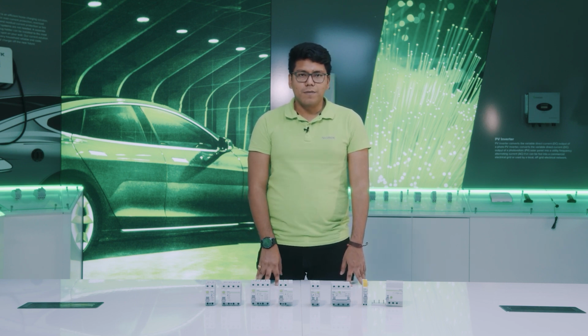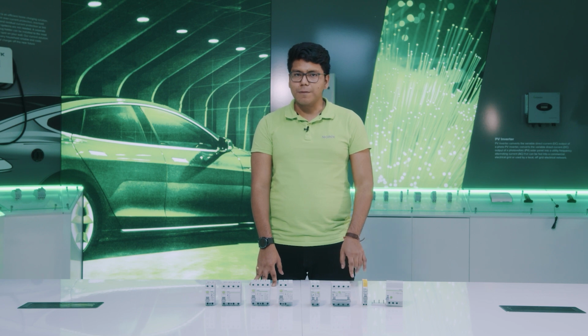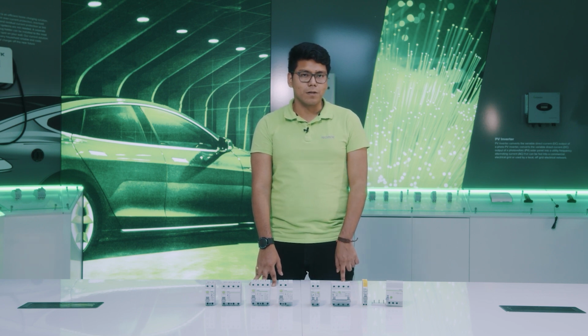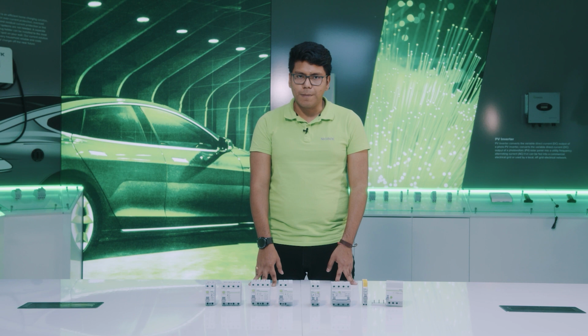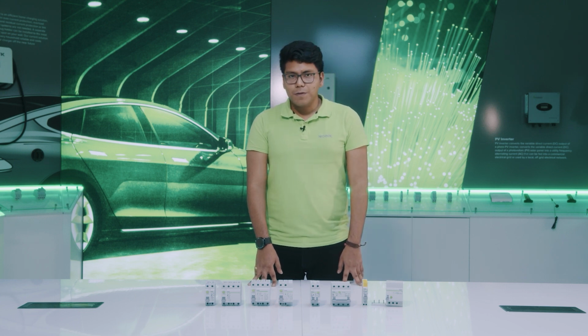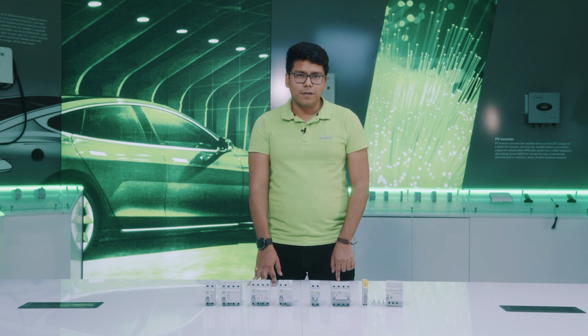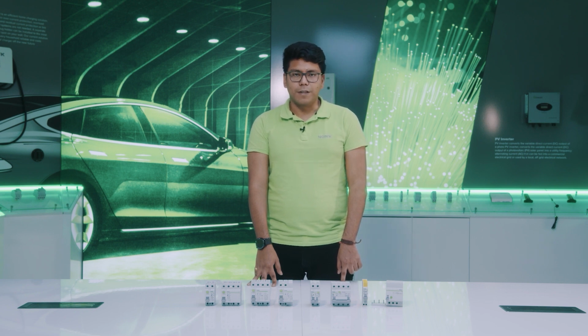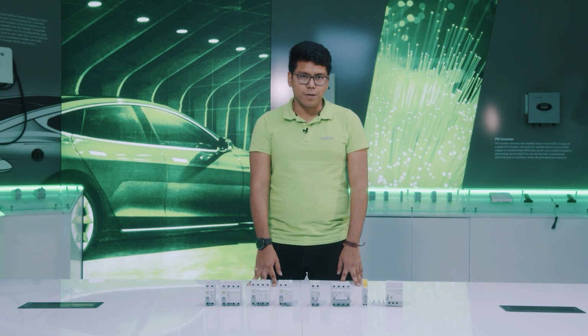As high sensitivity values we take 10 milliamps, whose usage is mainly in hospitals, where safety is the most mandatory. 30 milliamps. This value is the most used and can be found in every application. Electrical current is dangerous to our bodies, and 30 milliamps is the limit from which our body can suffer from heart fibrillation or arrest. As medium sensitivity values, we take 100 and 300 milliamps, which are used in buildings to protect us from fires. The 500 milliamps value is used for protecting machinery.